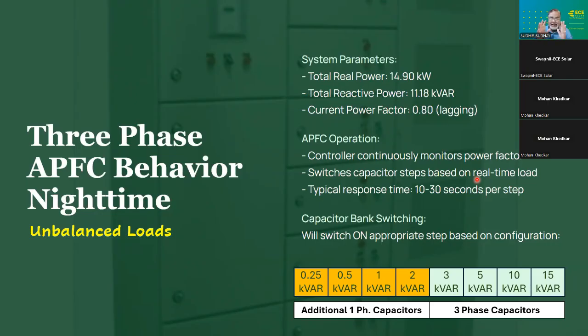So what is suggested? What is ideal? Ideal is we have a APFC where we have three-phase capacitors also, and we have single-phase capacitors, each for three different phases. So ideally, whichever is the lowest value by calculation from the relay, the three-phase capacitor first gets on, whether 3 kVAR, 5 kVAR, 10 kVAR, 15 kVAR, whatever. And whatever is the extra compensation required for that particular phase, Y phase, B phase, whatever, is compensated by a particular single phase bank.